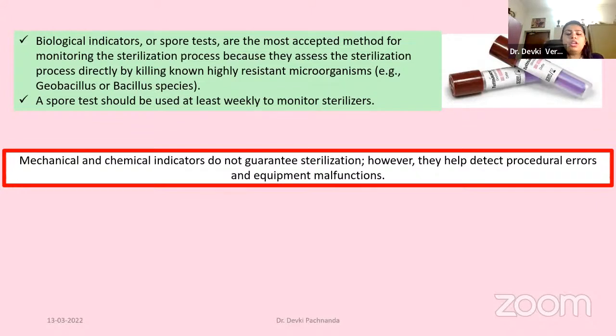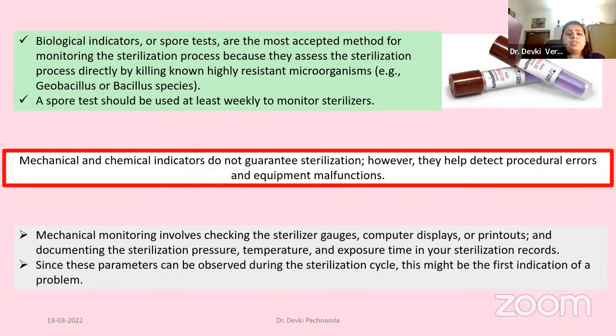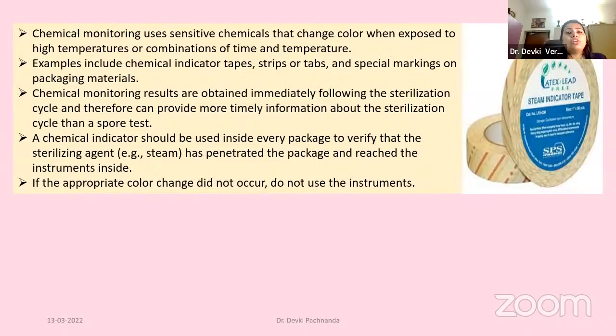These are more immediate in knowing if sterilization has taken place. So mechanical monitoring is very simple. That is seeing the sterilizer gauges, the computer displays, printouts, seeing that there is adequate temperature and pressure. It is mostly mechanically observing that everything is in place. Chemical monitoring is more sensitive, to see that there are chemical changes that take place at higher temperatures. So this includes chemical indicator tapes and strips, which are used within every package, inside and outside, to see if the heat has penetrated inside as well as on top. So it is placed inside every package and you have to see an appropriate change in color.